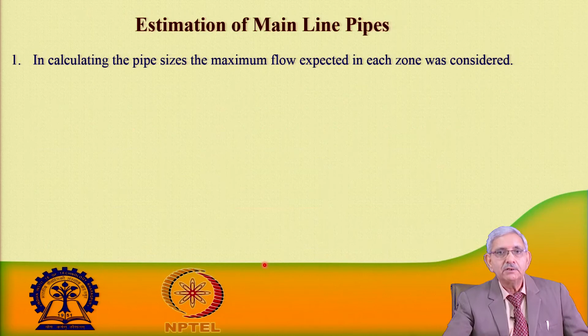So, in calculating the pipe sizes, the maximum flow expected in each zone has been calculated. We are assuming some other things as well: the length of pipeline connecting with the source of power is 10 meter, and the two irrigation plans, which I have already discussed, are to be operated in shift 1 and shift 2. When we are using irrigation plan 1, the requirement is 100 meter of 63 millimeter pipe, then 100 meter of 75 millimeter, and 110 meter of 90 millimeter pipe size, considering the optimal flow criteria.